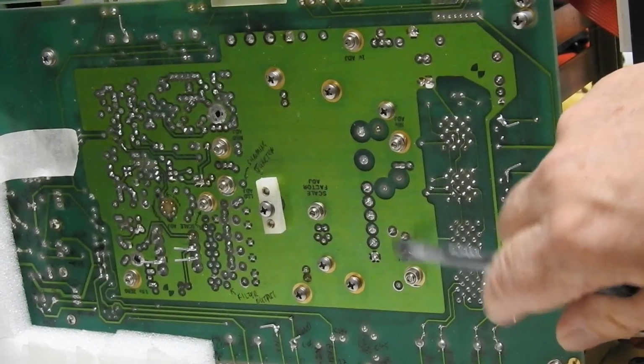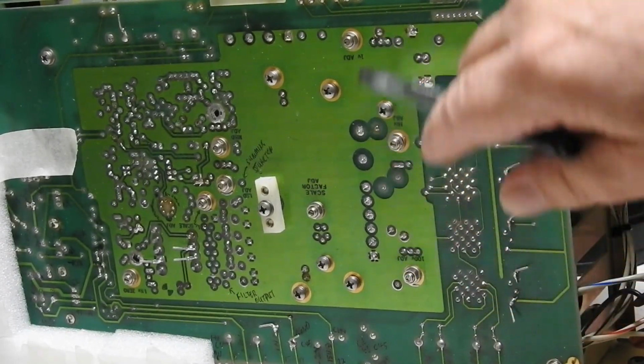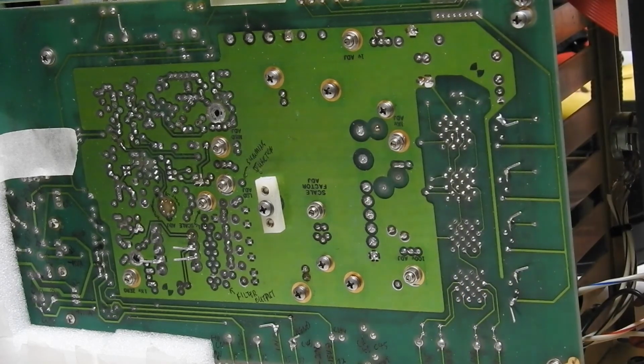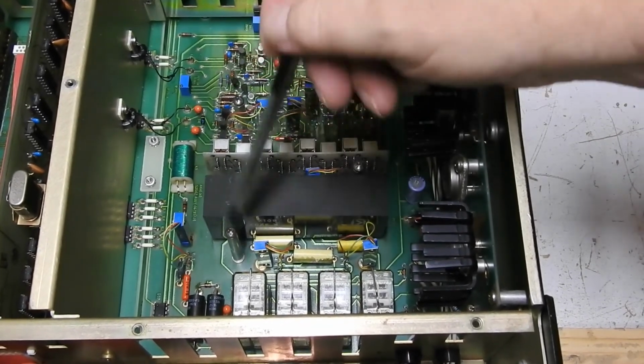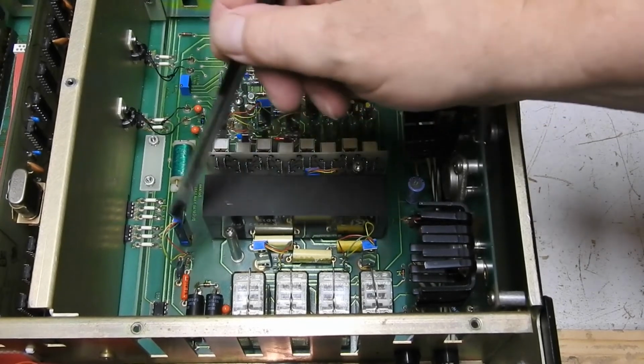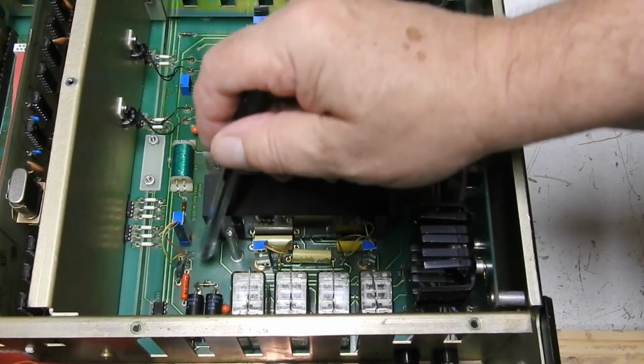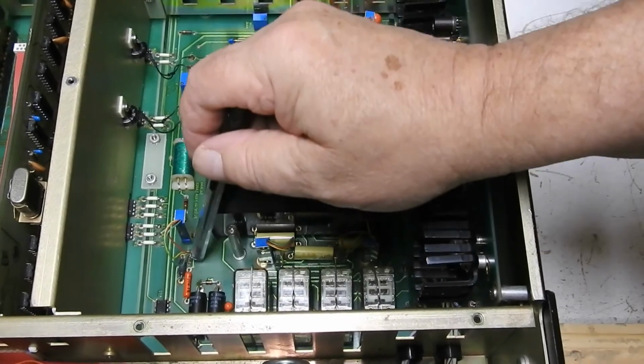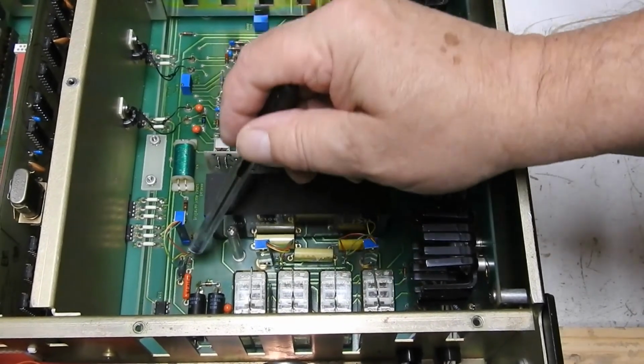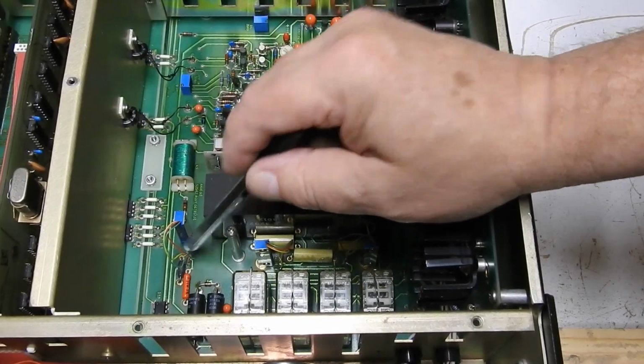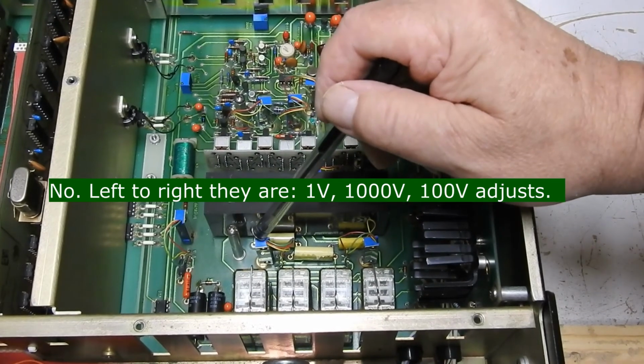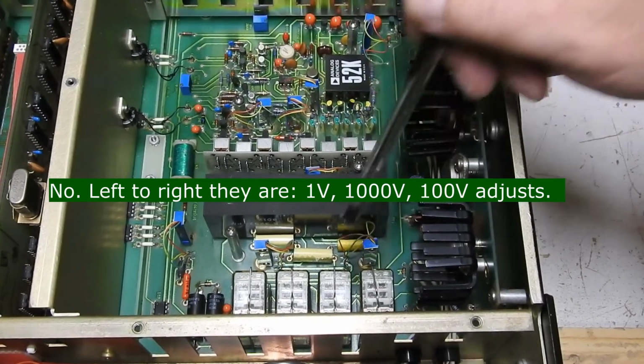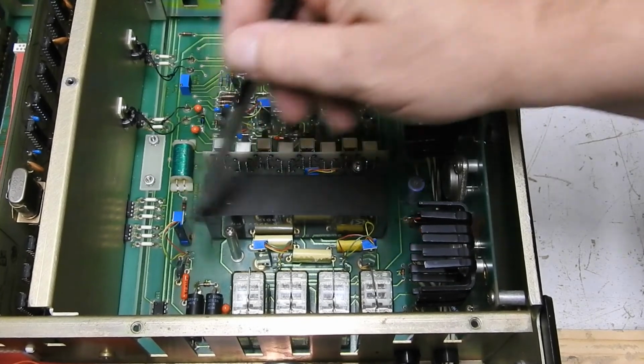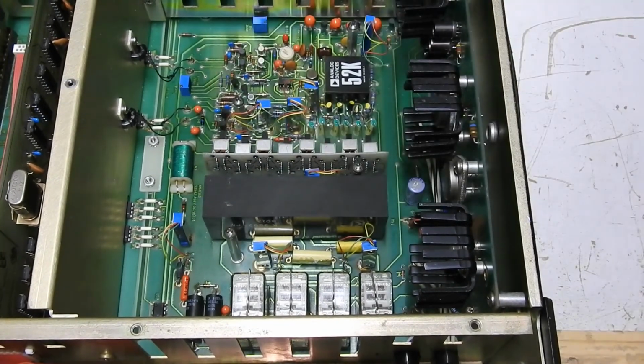I'm now looking at these 3 trim pots which are sitting across some of the points on that. So I'm talking about these 3 trim pots in particular. They're the ones that connect to various points on this potted module, and they have wires from the end that go down the printed circuit board. And I'm getting some strange readings looking across the 3 wires on the PCB. This one had, if you remember, 1 loose wire. That's the 1 volt adjust. I think this is the 100 volt adjust and the 1 kilovolt adjust, and that's the scale factor adjust. So yeah, those 4 pots, I'm getting some strange readings. So I'll just have another look at them to be sure.